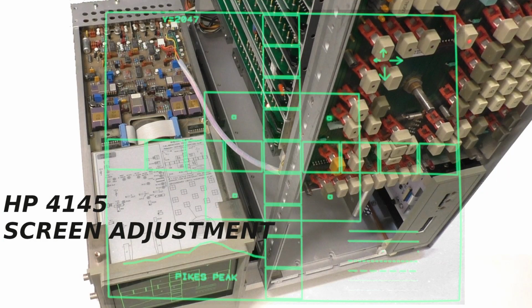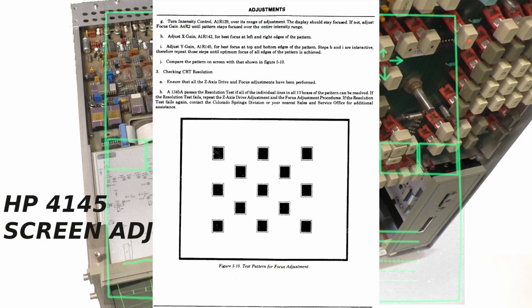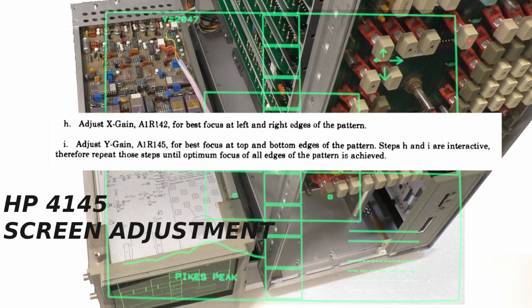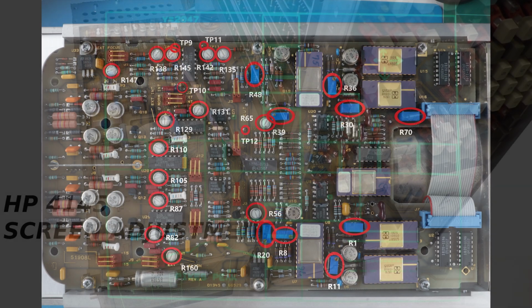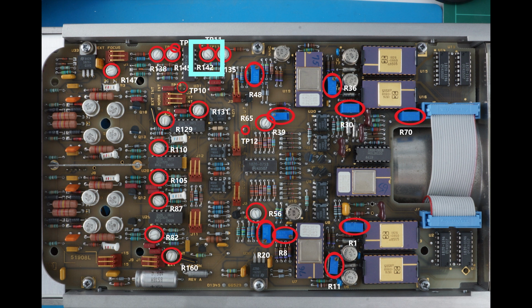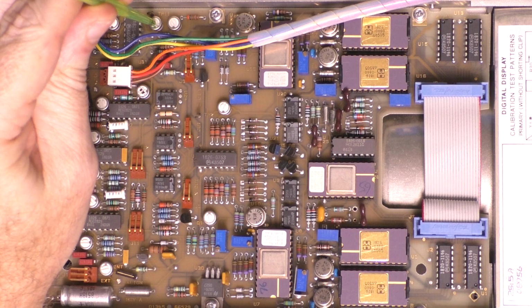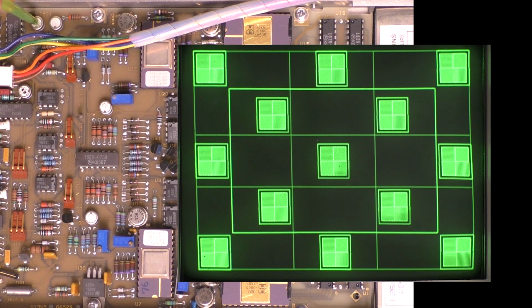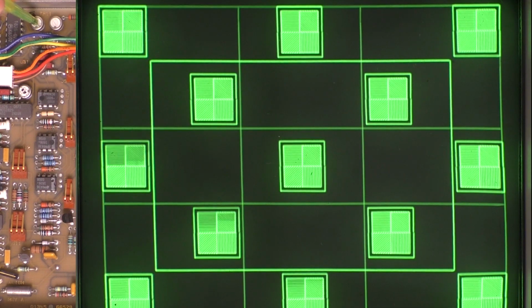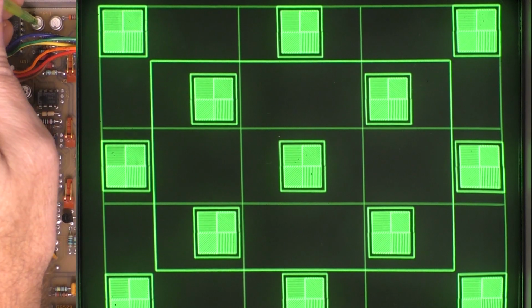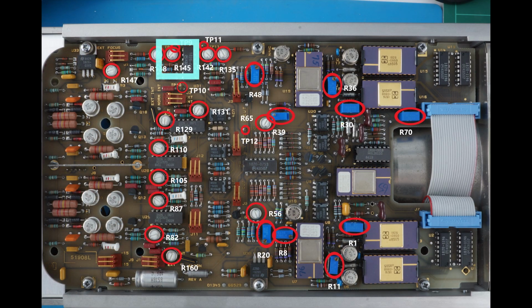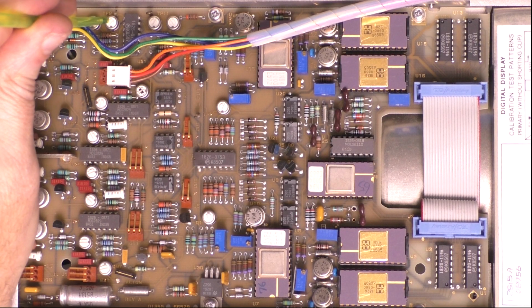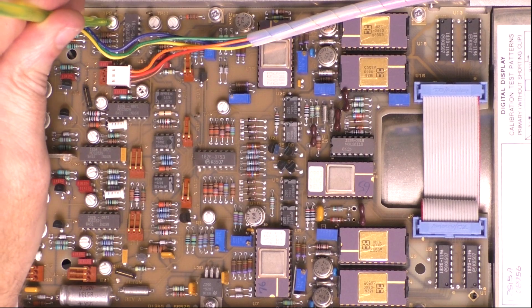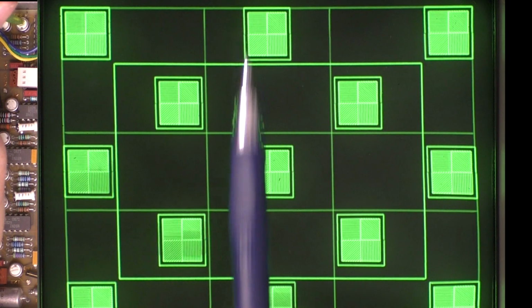We will move on to final parts of section 5-16-2, H and I, X gain and Y gain adjustments. Locate R142 on the A1 board. This adjusts the X gain. Adjust R142 so that the left and right edges of the test pattern are in optimum focus. Locate R145 on the A1 board. This adjusts the Y gain. Adjust R145 so that the top and bottom edges of the test pattern are in optimum focus.